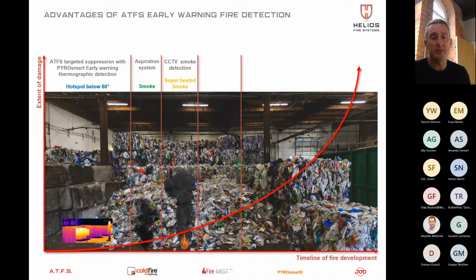Next is superheated smoke detection through CCTV smoke detection cameras, which we provide for customers who can't afford PyroSmart, and yes, they are good. But you will always have a flame, and a lot of superheated smoke, which can cause issues for the detection system to see what's going on, especially if the room fills with smoke rapidly before massive thermal runaway occurs. Again, you can see here we're getting lots of potential damage to the site and building, and the curve is starting to move very rapidly.